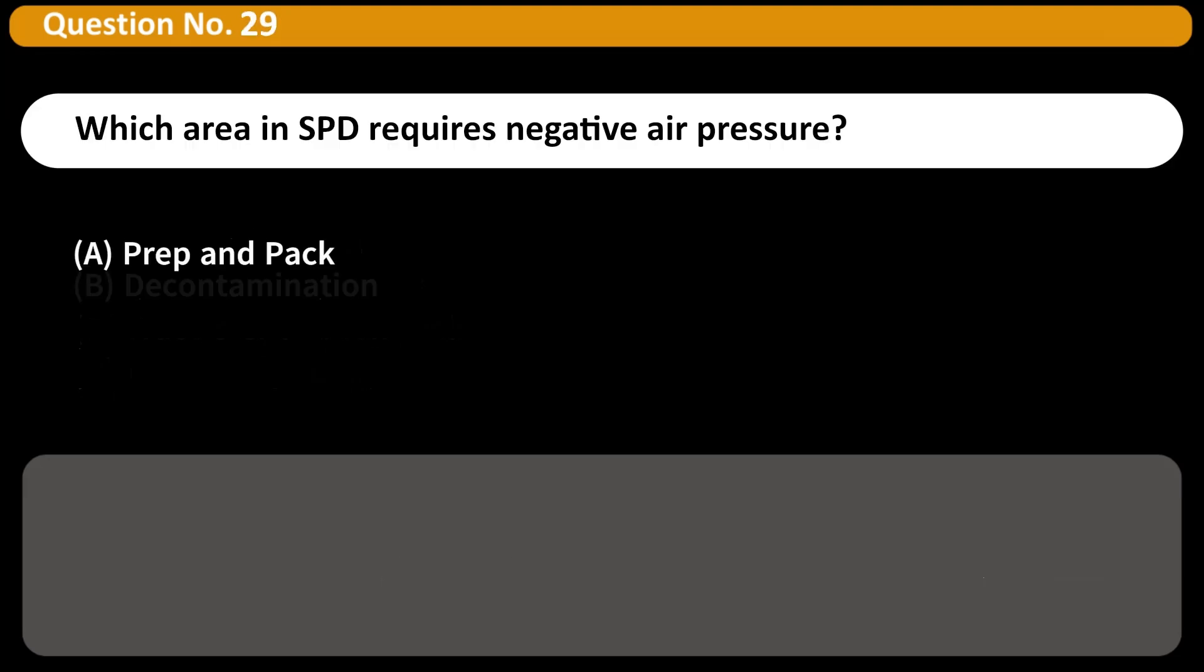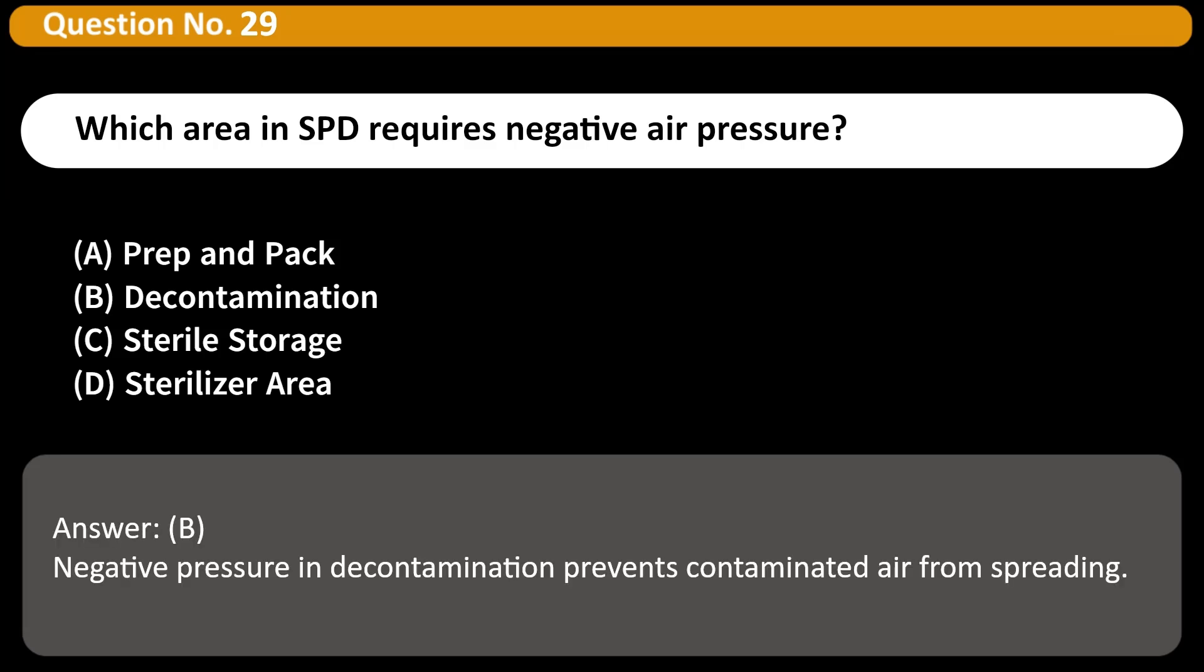Which area in SPD requires negative air pressure? A. Prep and pack, B. Decontamination, C. Sterile storage, D. Sterilizer area. Answer B. Negative pressure in decontamination prevents contaminated air from spreading.